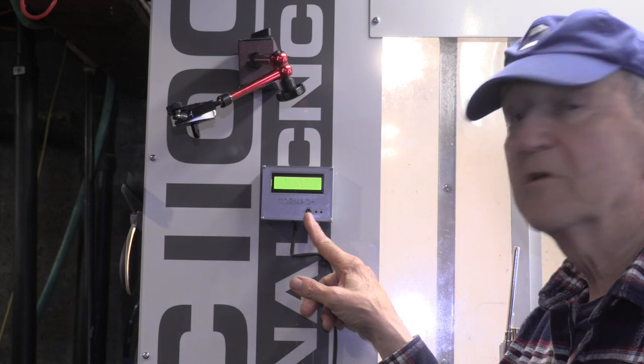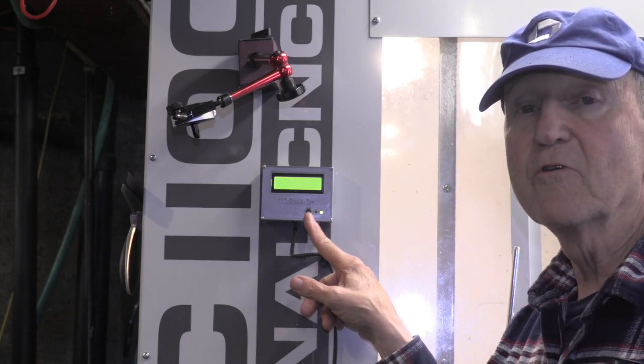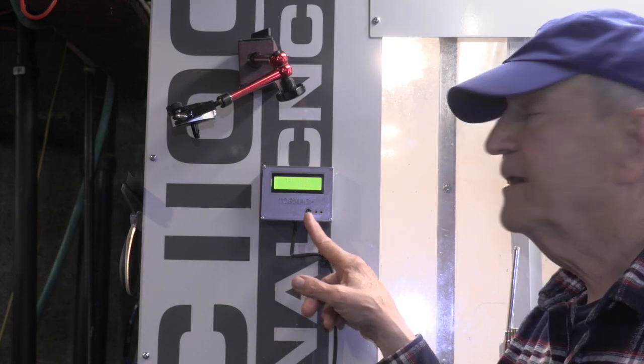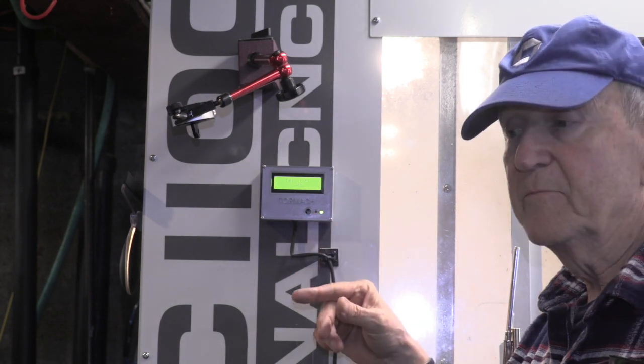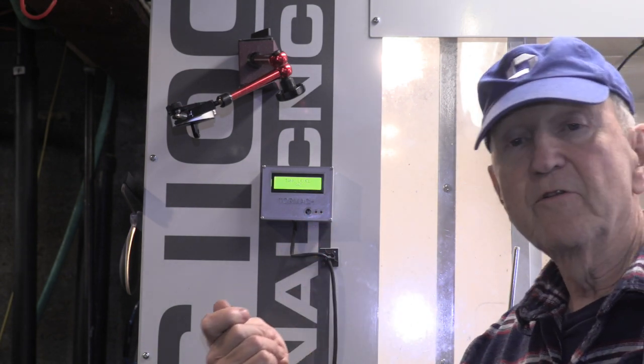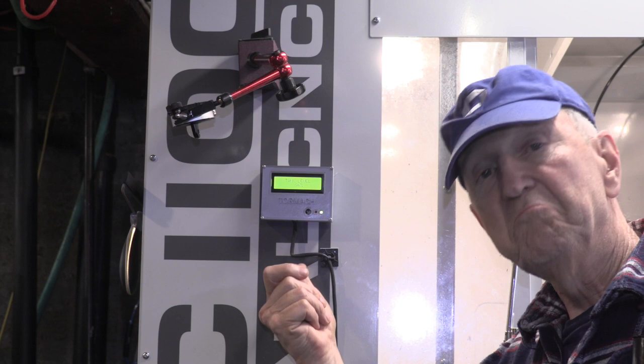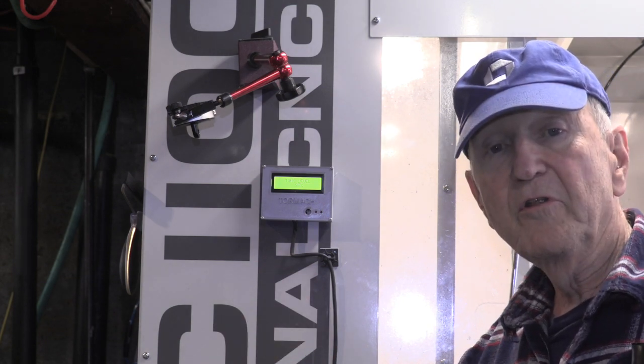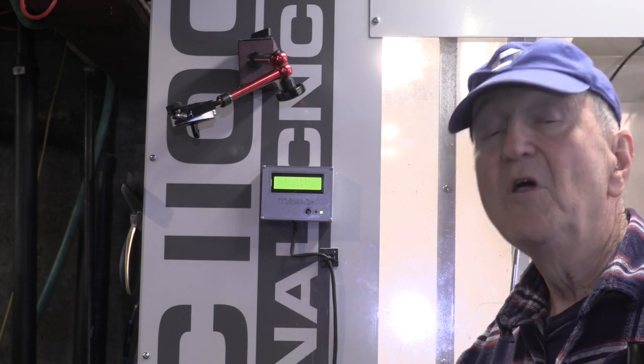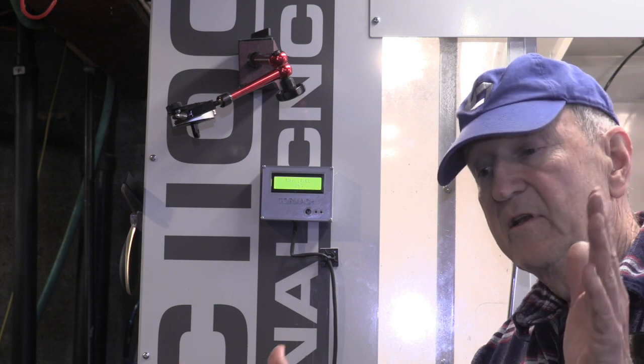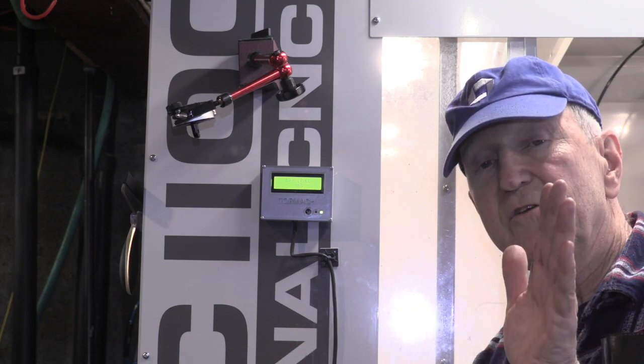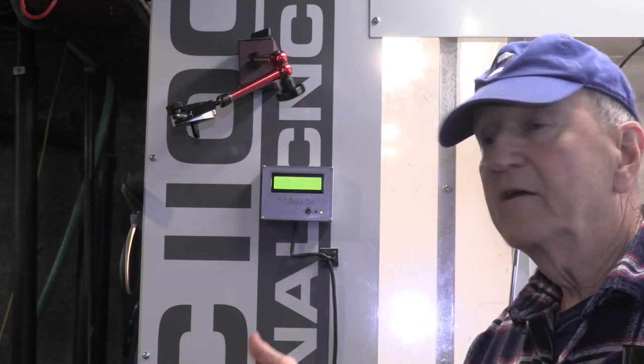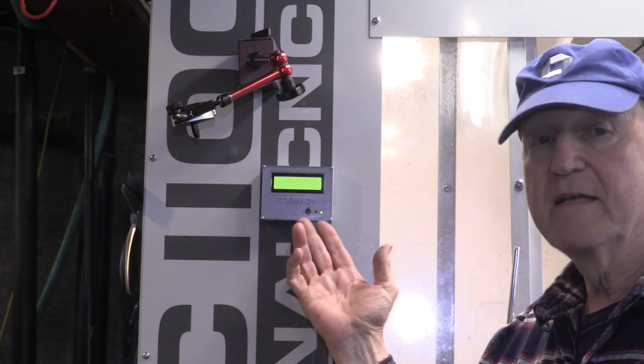You just push it with an eraser of a pencil or something like that, and then you can recalibrate the machine simply by raising the float to its maximum level, punching the button, lowering the float to its minimum level, and punching the button again. That tells the machine what the range of values are for the float, and the microcontroller does the rest.